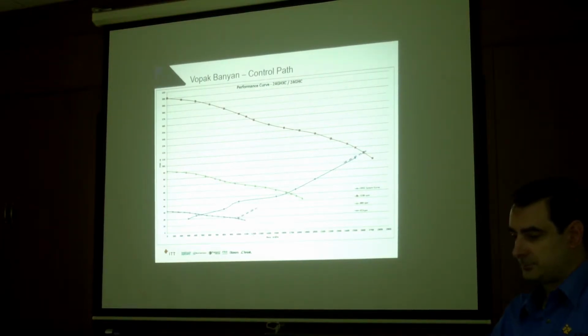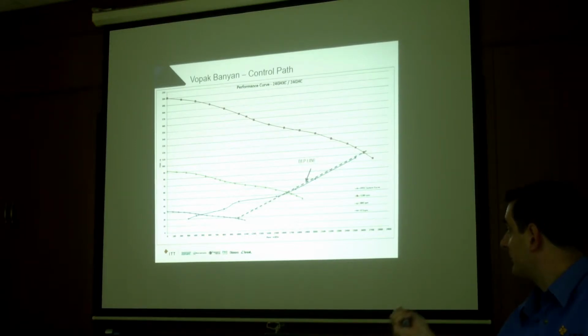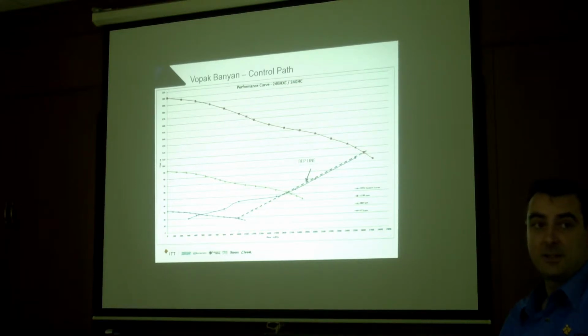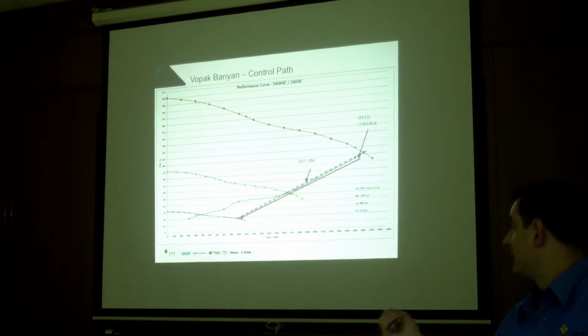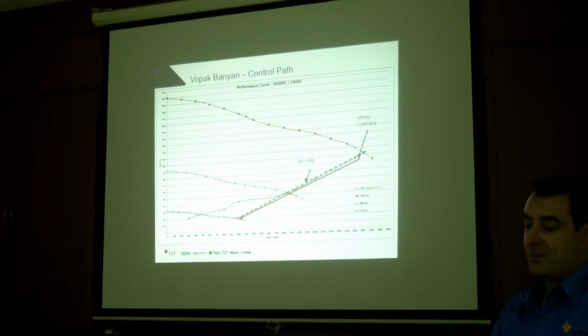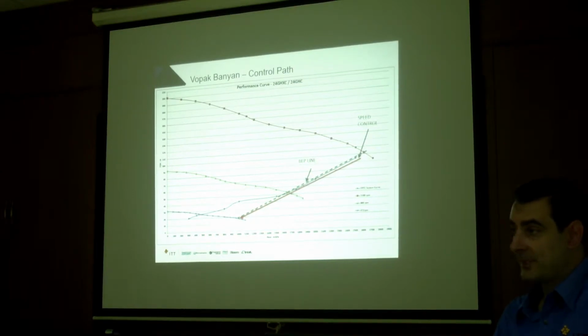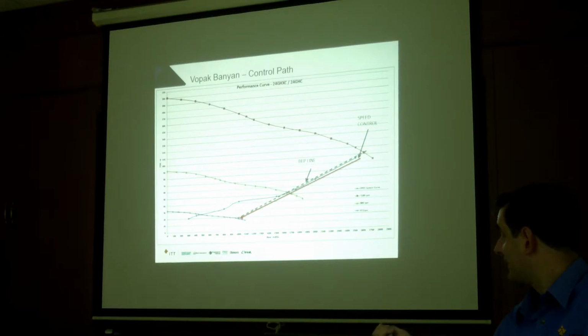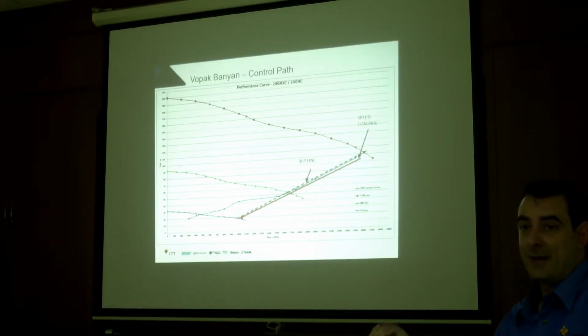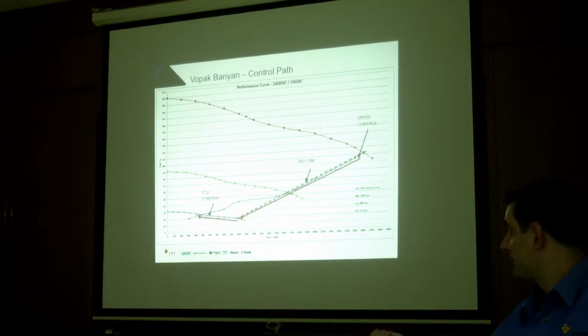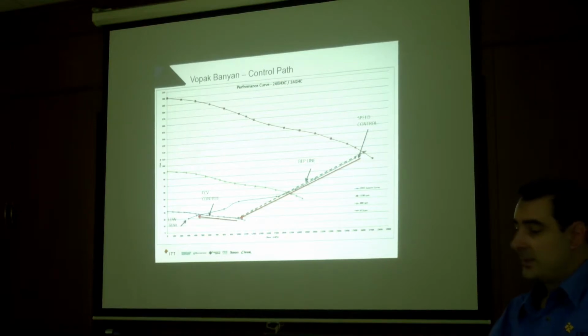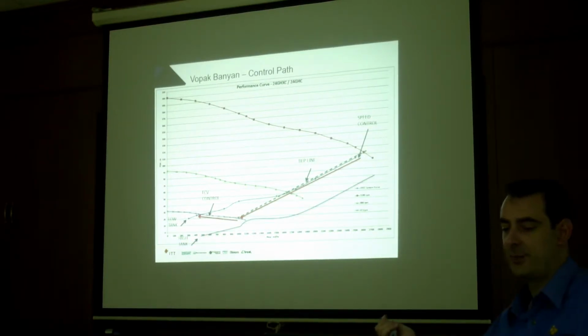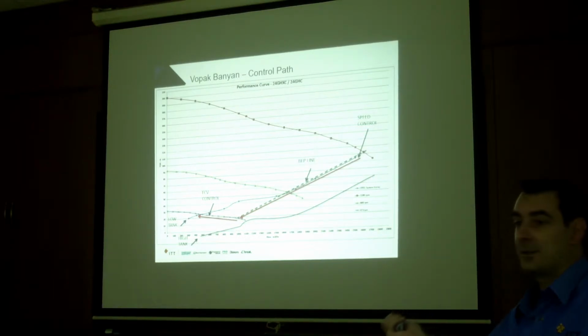How that works is like this. That was their system curve that they gave us. The selection meant that with this system curve, most of the time the variable speed drive will follow the BP line, the friction resistance versus the system curve versus the pump speed curve. So in that case, they will see speed reduce. But they also had a floating roof. If you've got any floating roof applications, the problem was down here: if they wanted 400 meters cubed per hour when they raise or lower the roof, sometimes it was difficult. So when that happened, we used the flow control valve to throttle back only at the last speed. This system curve was for low tank, but the problem was the system curve for high tank. So you can see we're off the end of the curve, intersection point.